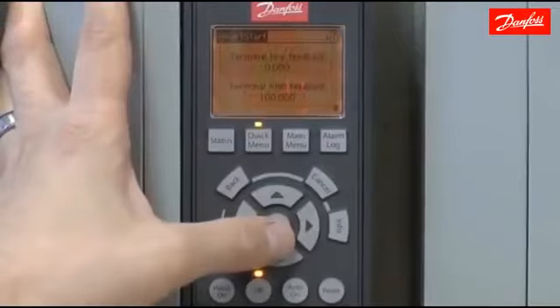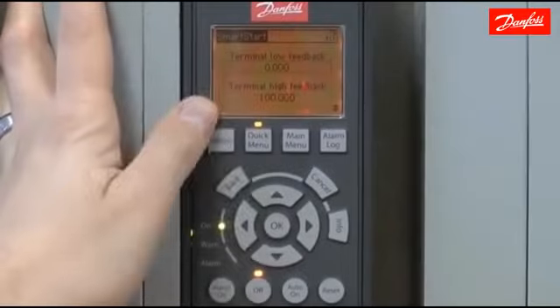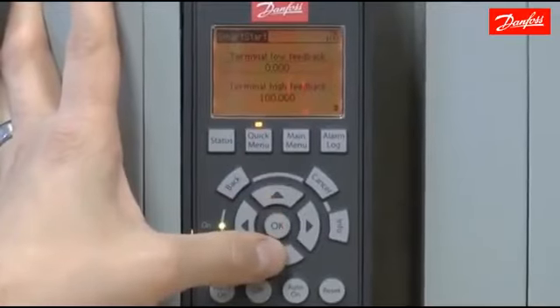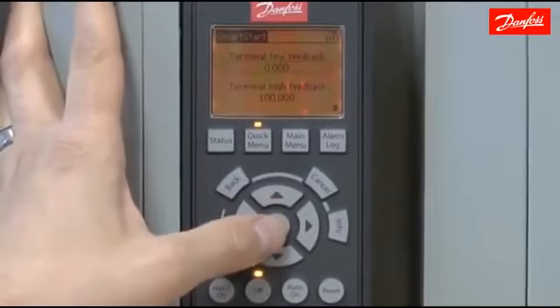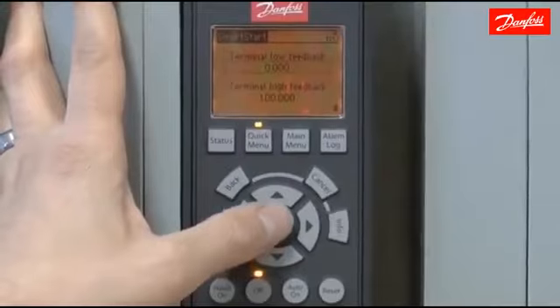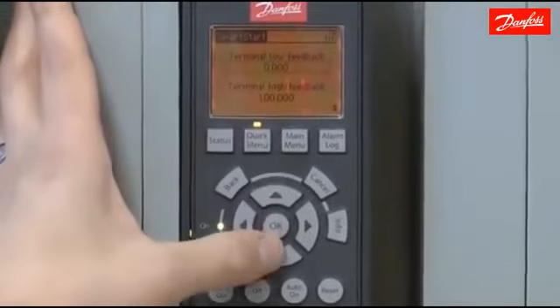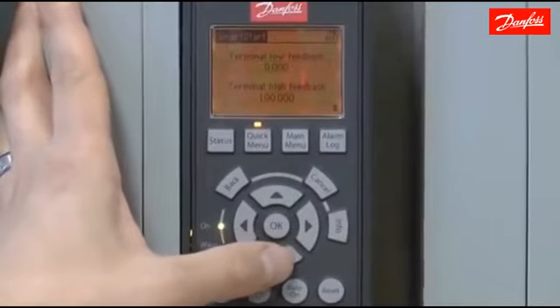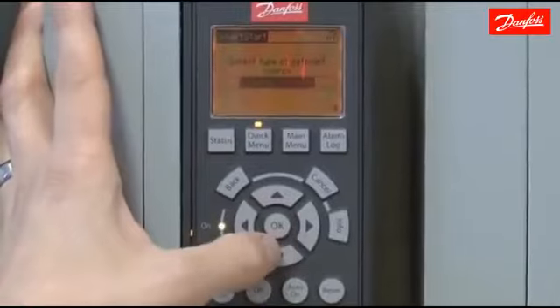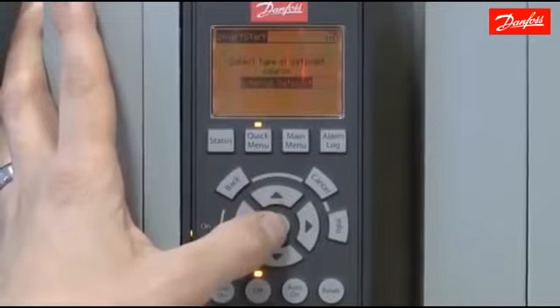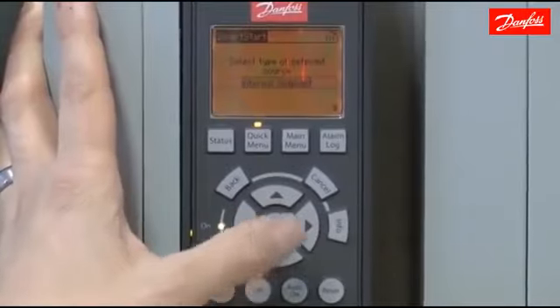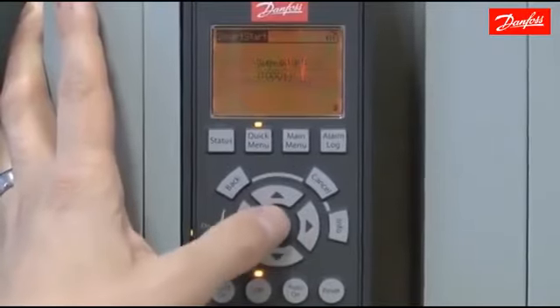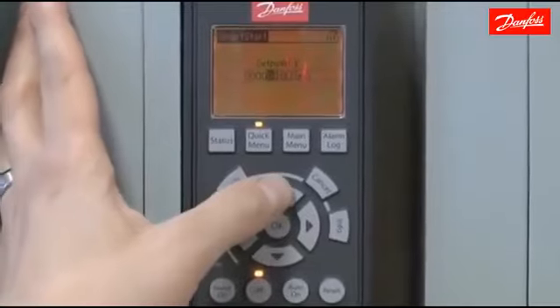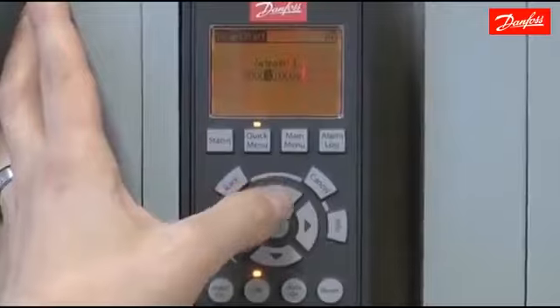Press OK to continue. Now it's going to ask me for the low and high feedback values of the transducer. The particular transducer I'm using is 4 to 20 milliamp equals 0 to 100 psi, so I'm going to leave those the default settings. Select the type of set point. I'm going to be using an internal rather than an external set point, so I'll choose internal here, move on to the next screen, and now I'll enter my set point of 75 psi.